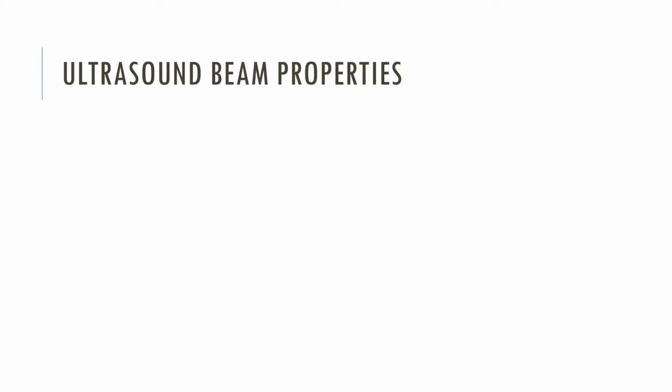Okay, so far in this course, we've assumed a single transducer element generating multiple sound waves. And we do this because it's mathematically simple to explain and it gets the point across. Once we create the sound waves at this transducer surface, they constructively and destructively interfere. Now in the very near zone, very close to the transducer, this starts to collimate the beam tightly and converges the beam towards a specific point at a distance.